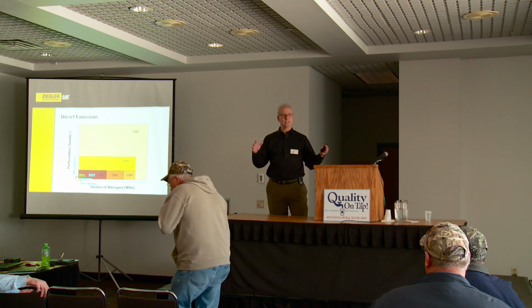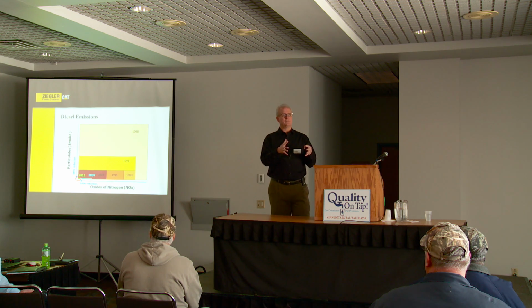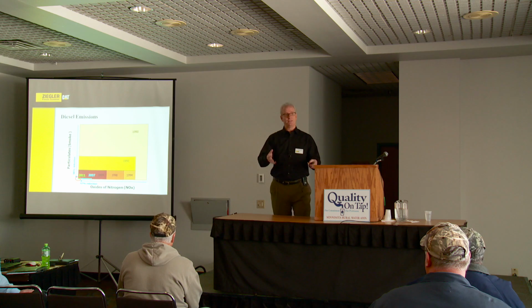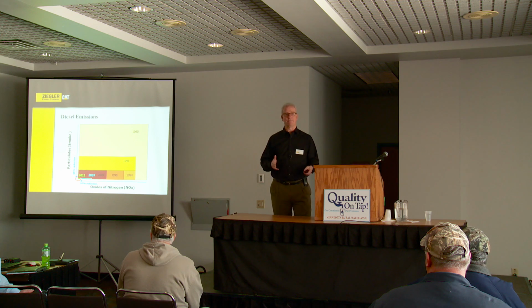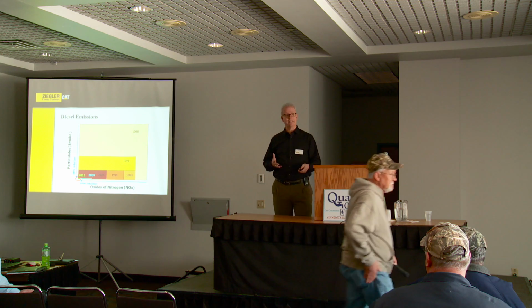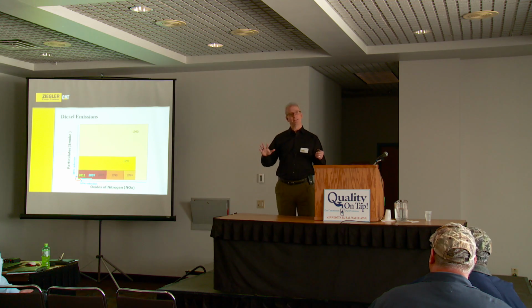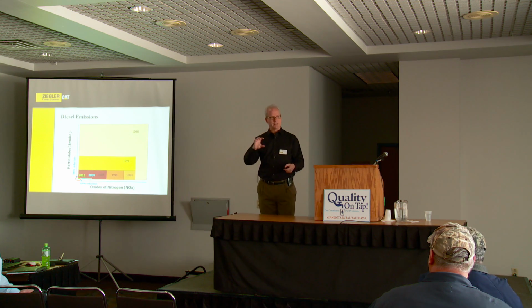The regulations have been put in place gradually, groups of years by years, to put out less emissions from new engines. As you can see, it's driven down to where we are today, beyond 2011, with this thing called Tier 4, where there's a 98% reduction in particulate matter, smoke, and a 97% reduction in NOx. So big reductions over time, happening gradually and in different time windows. This is the picture for diesel generators, but if it was a diesel truck, those dates would be earlier.